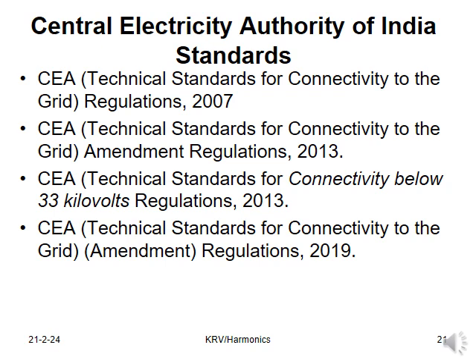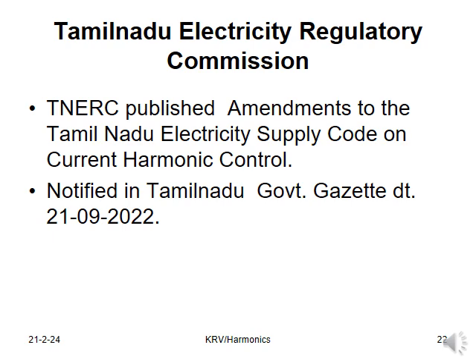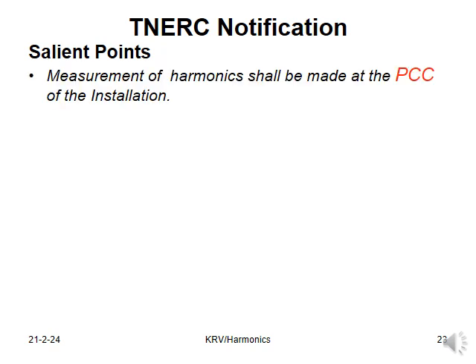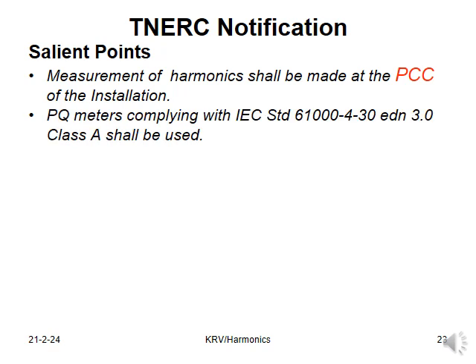The Central Electricity Authority of India published standards for harmonic controls in the years 2007, 2013 and 2019. Based on those standards, the Tamil Nadu Electricity Regulatory Commission published amendments to the Tamil Nadu Electricity Supply Code on current harmonic control and notified in the Tamil Nadu Government Gazette dated 21/9/2022. The salient points of the TNERC notification are: measurement of harmonics shall be made at the PCC, point of common coupling, of the installation. Power quality meters complying with IEC standard 61000-4-30 edition 3 class A shall be used for measurement.